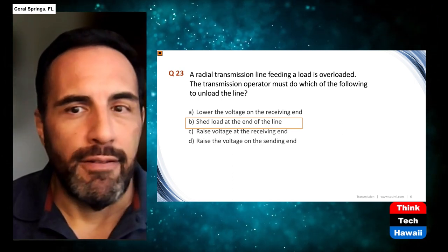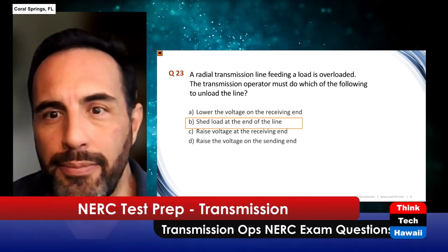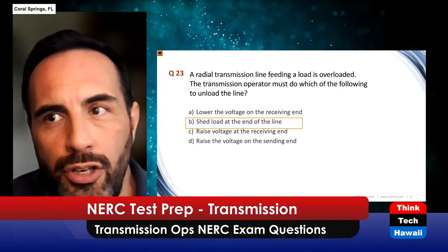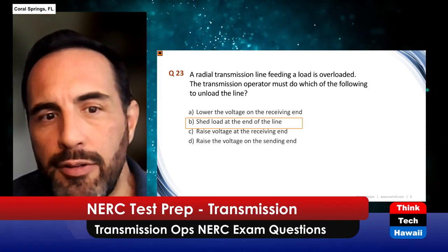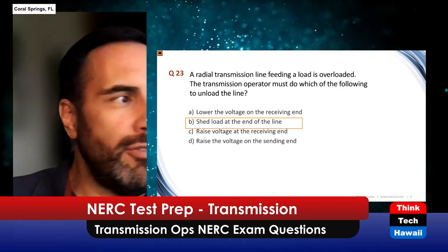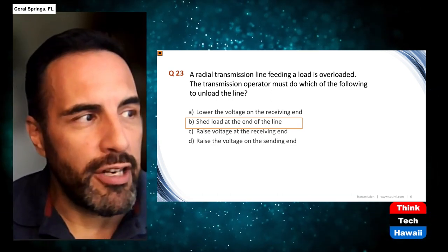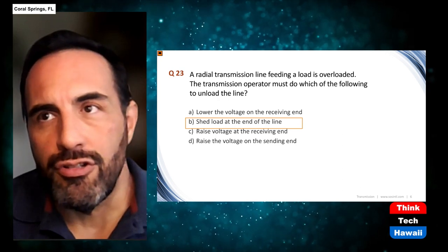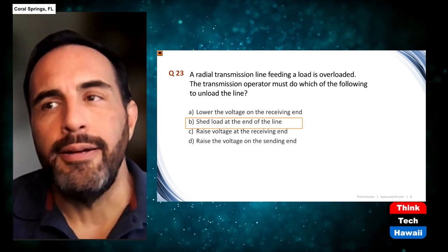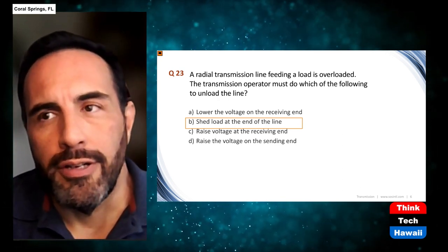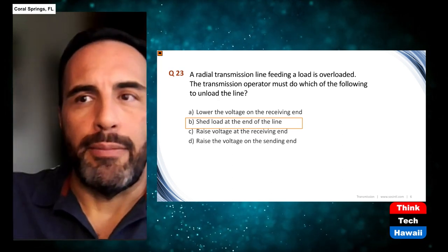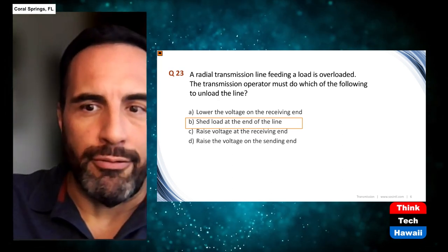If you try and lower the amount of power coming in, you're still going to cause other problems because you're going to depress voltage. So here, the only solution really is to shed load at the end of the line, which usually when something is radially fed, is the only solution, unless you have generation that can be started and brought online at that radial end.